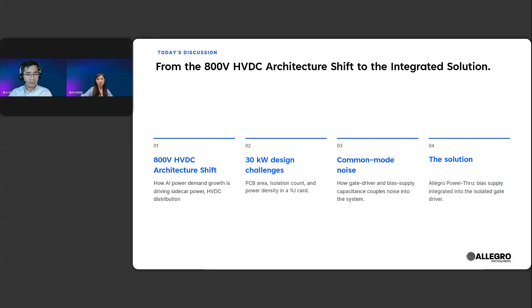Before we go into PSU design, I want to first highlight one important architecture change in AI server power. In traditional server power architecture, power conversion is more closely integrated inside a server rack, and it is a low voltage system. Nowadays, AI chip power consumption keeps increasing, and the traditional 48 volt system's approach reaches its physical limit. The high current brings more copper, large cables, and more space pressure inside the rack. Thermal management efficiency also becomes a problem.